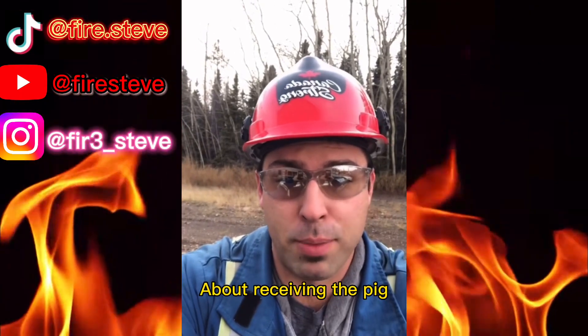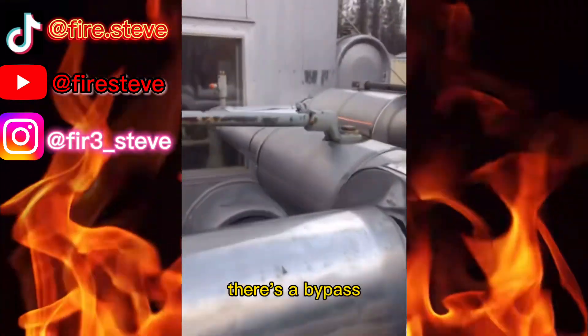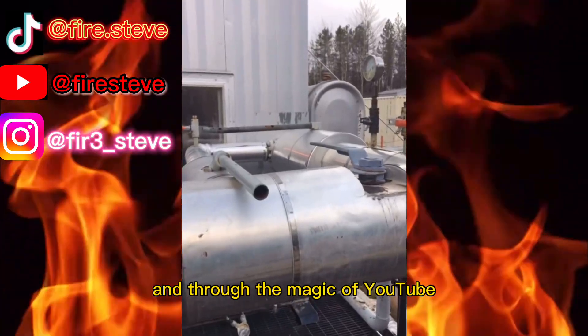Since I have you all here, we'll talk about receiving the pig. So much like sending the pig, there's a bypass. We're gonna open this bypass line and then I'm gonna shut these two valves here to isolate the pig barrel. And through the magic of YouTube, we're isolated.